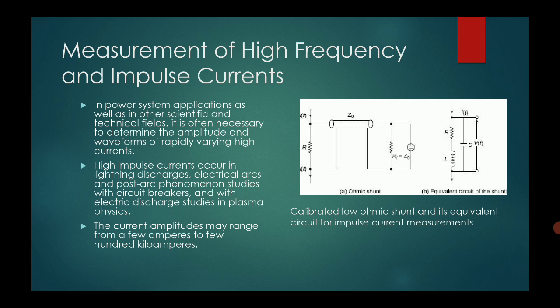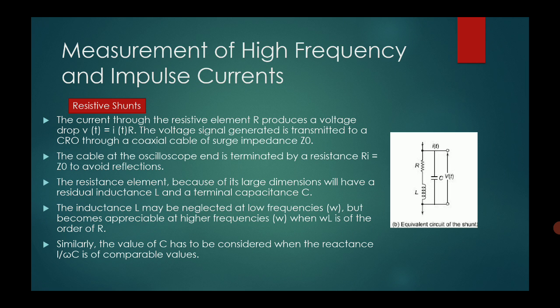Moving to measurement of high frequency and impulse currents. On the right-hand side we have a calibrated low ohmic shunt and its equivalent circuit for impulse current measurement. In power system applications as well as other scientific and technical fields, it is often necessary to determine the amplitude and waveform of rapidly varying currents. High impulse currents occur in lightning discharges, electrical arcs, post-arc phenomena studies with electrical breakers, and electric discharge studies in plasma physics. Current amplitudes may range from a few amperes to a few hundred kiloamperes.